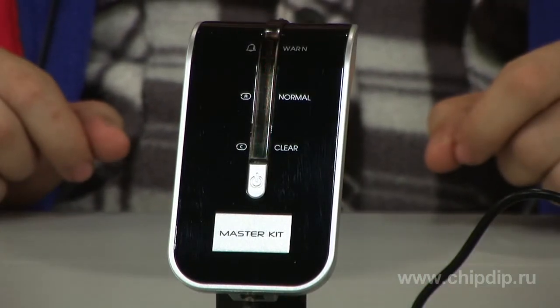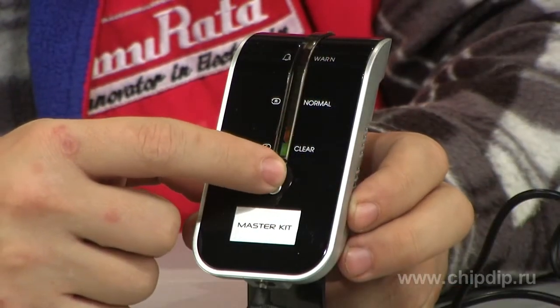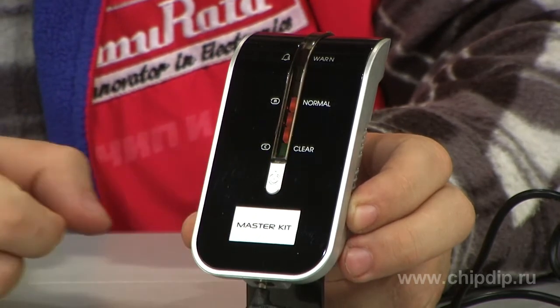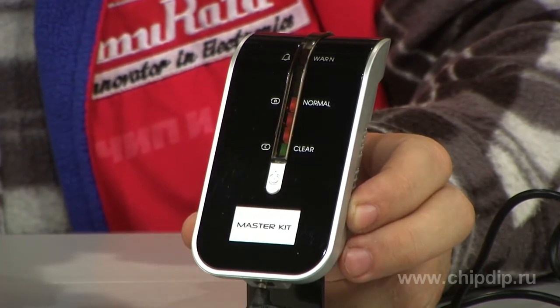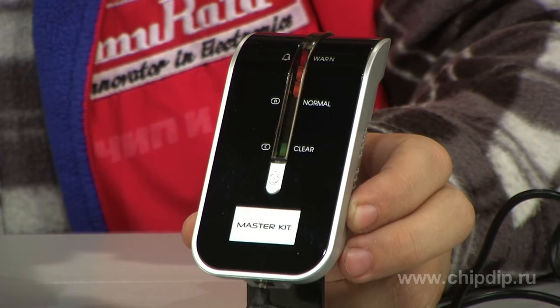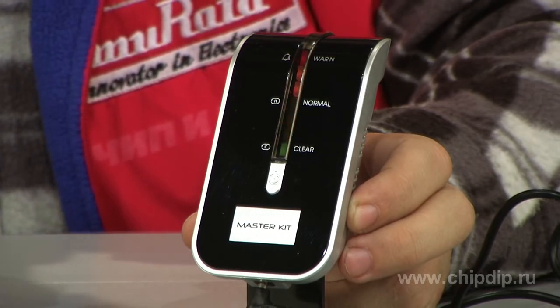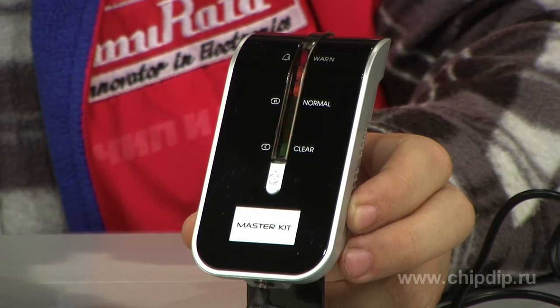The device will start automatic calibration. You can also calibrate the device manually. To do this, press and hold the key for more than 2 seconds. Once you hear a beep, release the key. This starts the process of recording ambient air quality to the memory. Within 3 to 5 minutes, the recording process will be completed. It will be notified with a double beep.